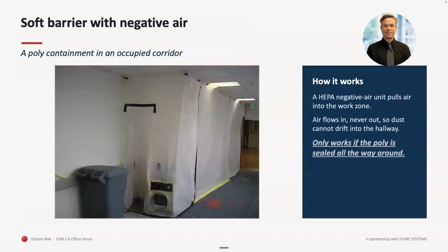Here's something that doesn't meet the requirements any longer, never did, and this is a barrier that when I see these type of barriers put up, I really kind of frown because one, it probably was a little bit disruptive to put up. It's a plastic barrier that meets the fire rating. However, it has like a triple flap or a flap. We don't allow those any longer.